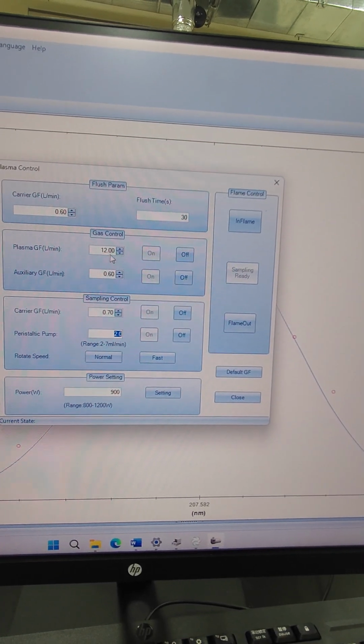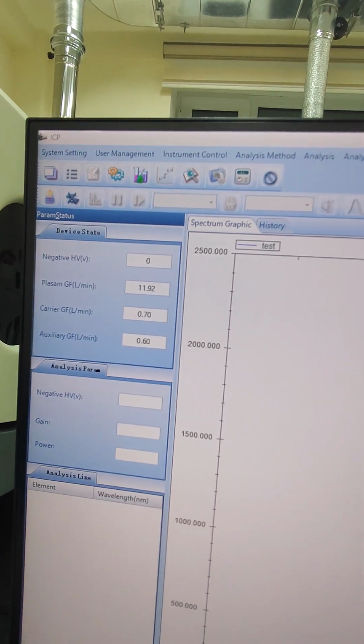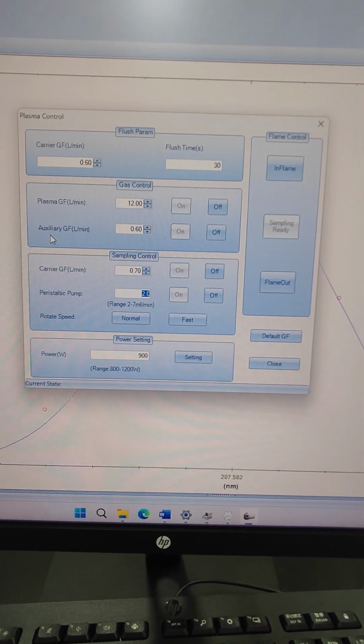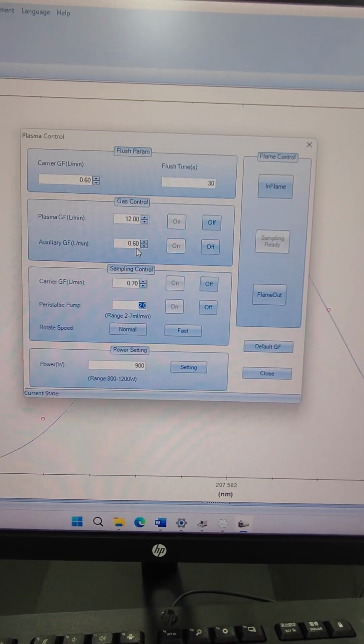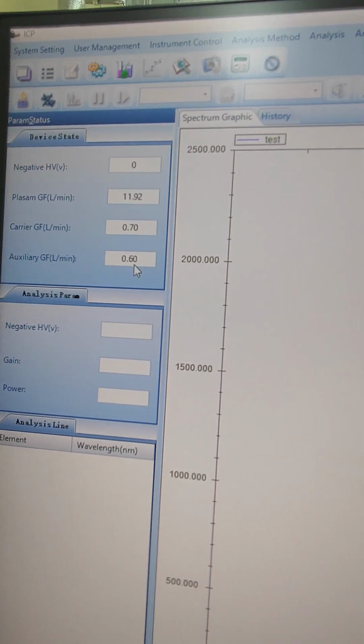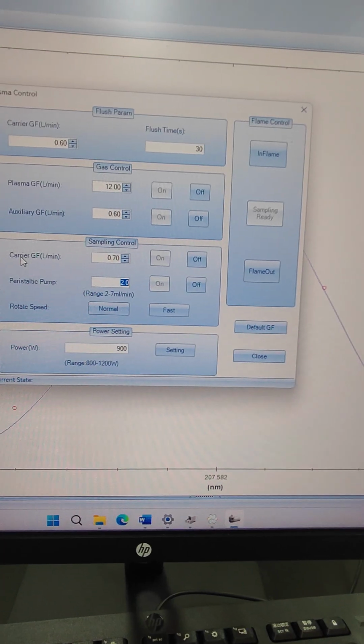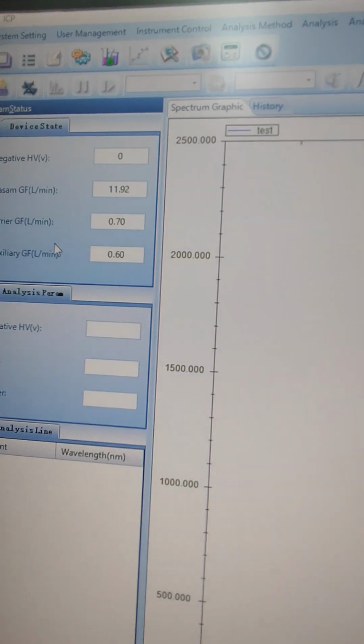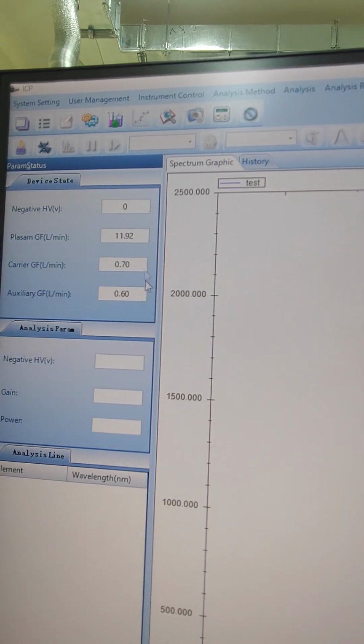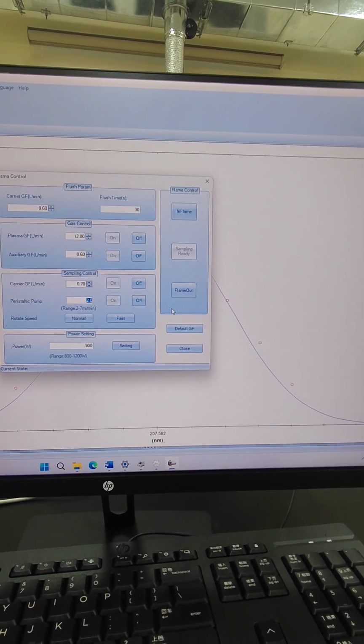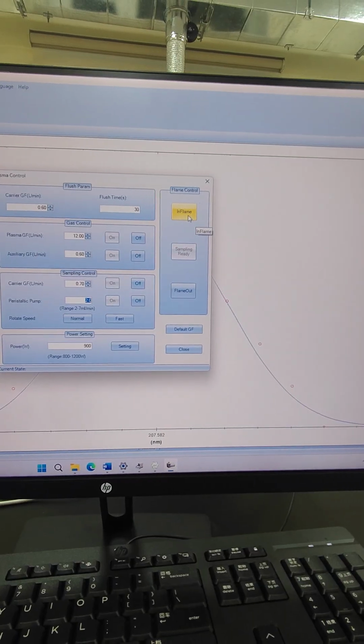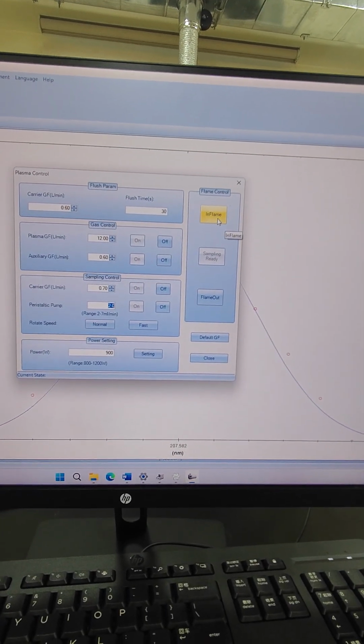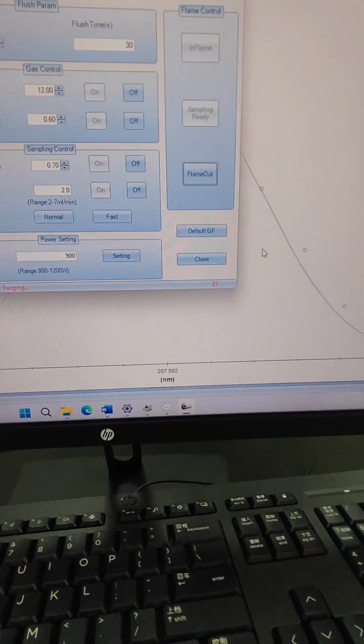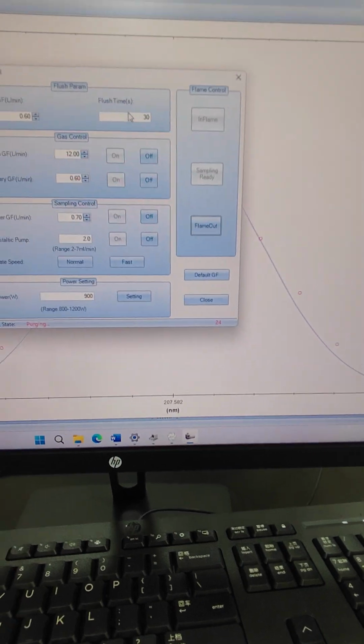The plasma flow is 12, and here is also 12. The GF is 0.6, here also 0.6. The carrier is 0.7, here also 0.7. This is the real-time one. That means it's good. For the others, you need to check, and then we can ignite. When it's ignited, it will give a count of 30 seconds. That means the flush time.